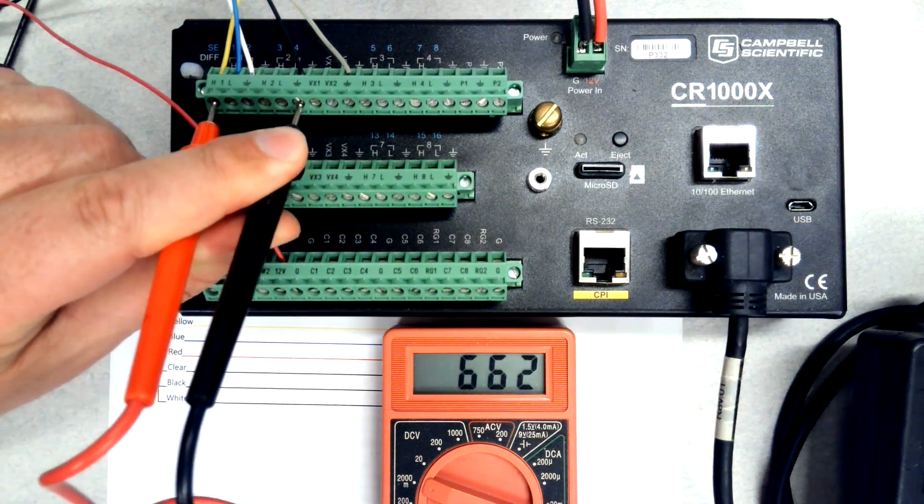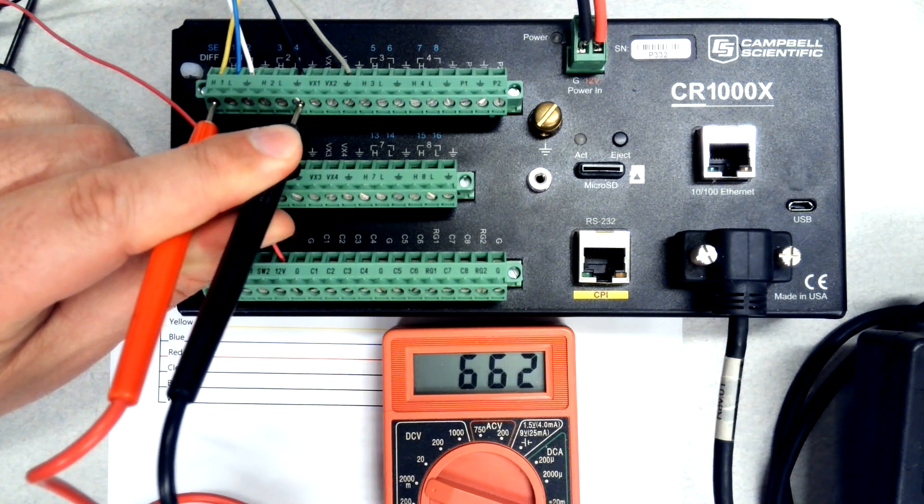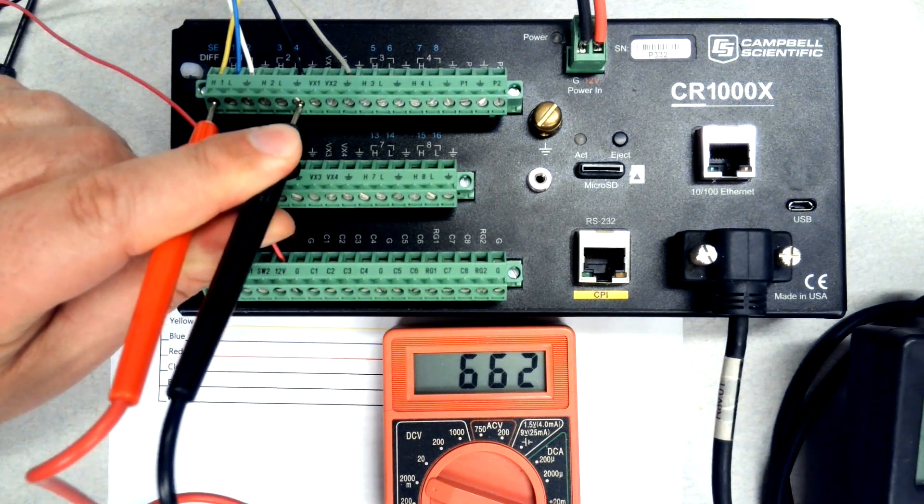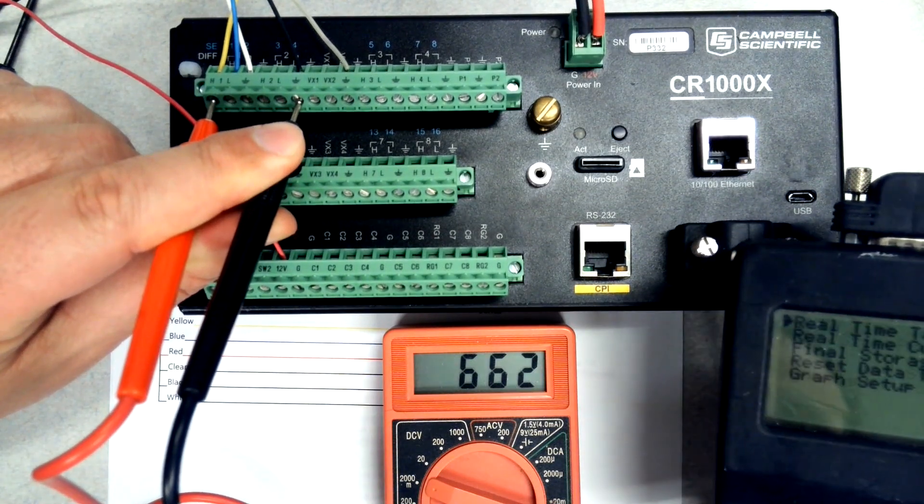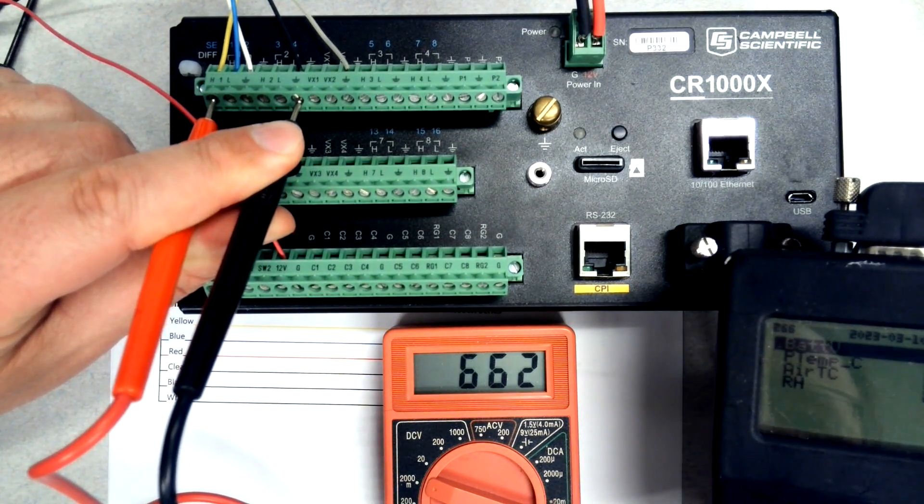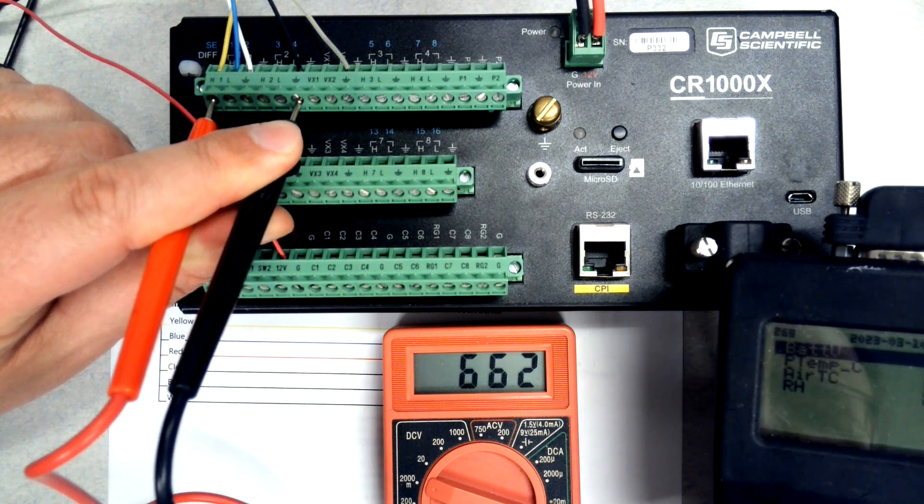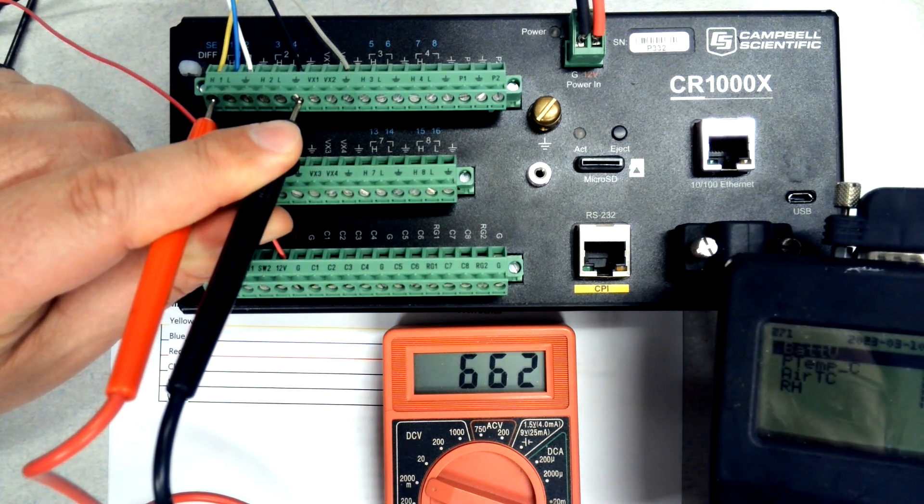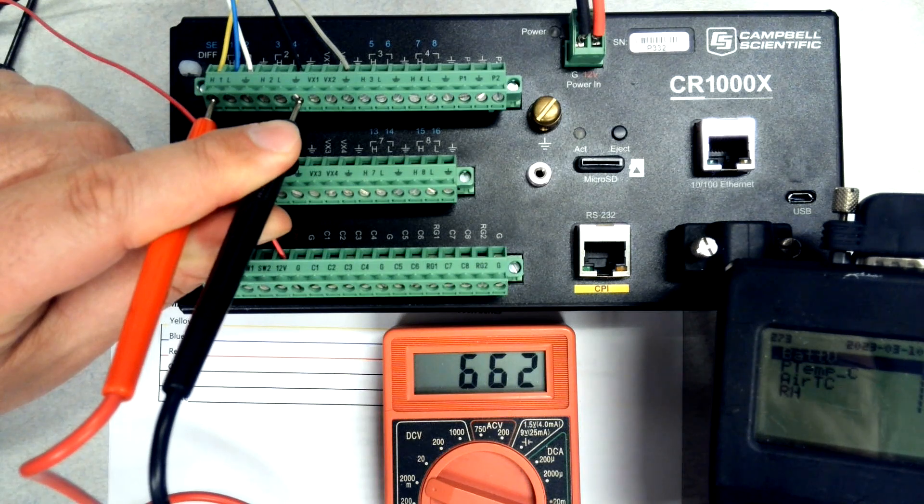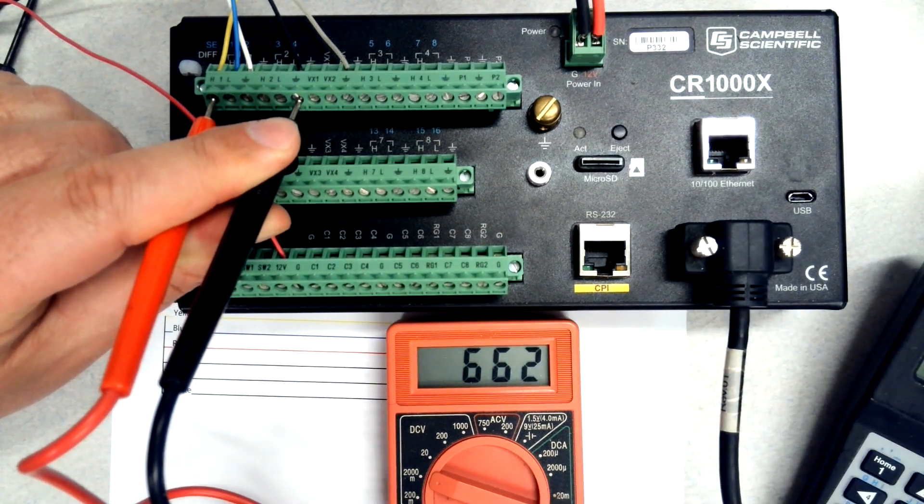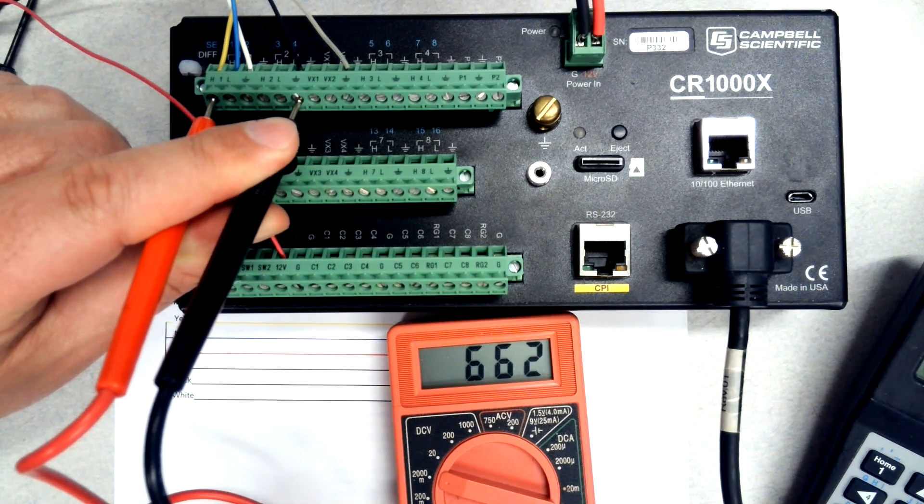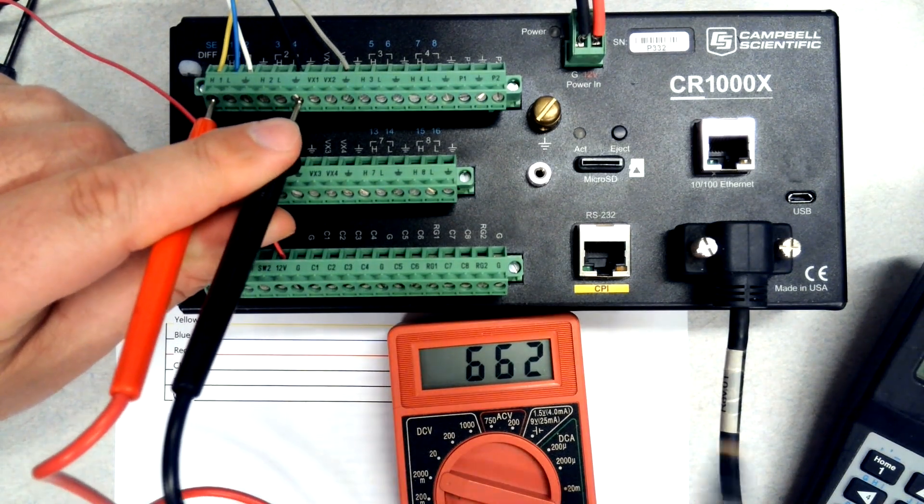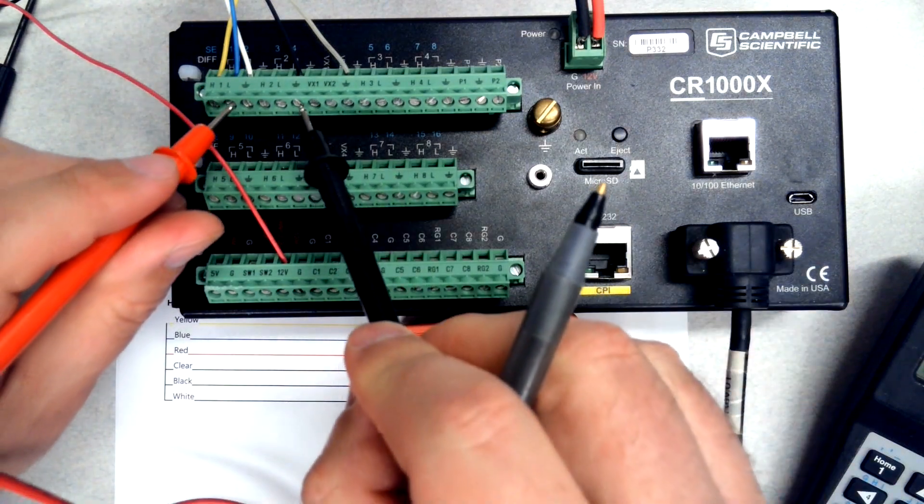That's reading 662, so I'm going to make a note of that. At the same time I need to look at my display and make a note of what my temperature is. Right now, my temperature according to my display is 25.6.